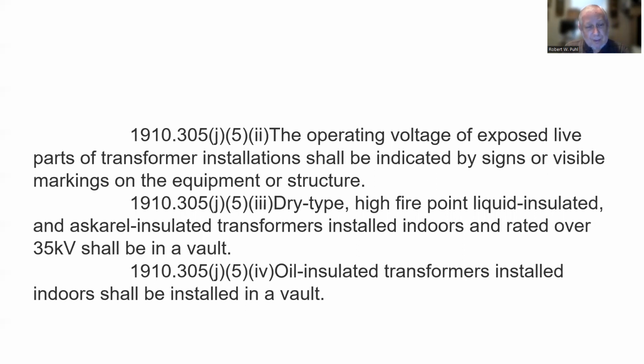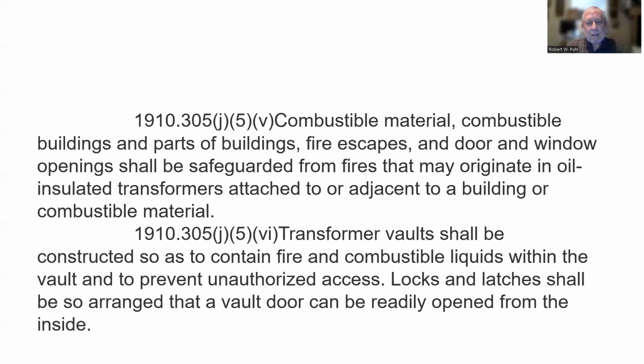Oil insulated transformers installed indoors shall be installed in a vault. Makes sense. Combustible material, combustible buildings and parts of buildings, fire escapes, and door and window openings shall be safeguarded from fires that may originate in oil insulated transformers attached to or adjacent to a building or combustible material. So in other words, they're saying anything combustible and fire escapes, doors, and window openings have to be safeguarded from this transformer. Transformers catch on fire sometimes.